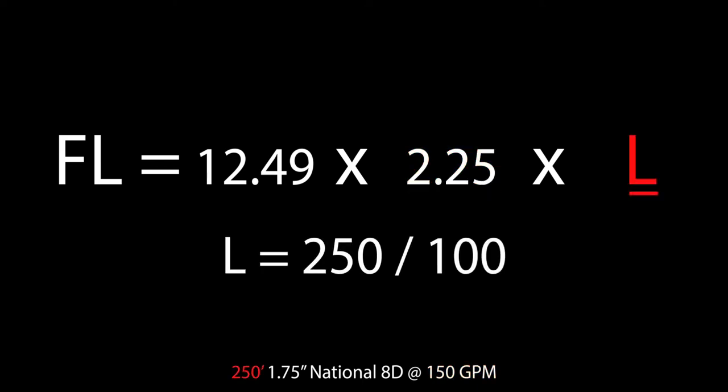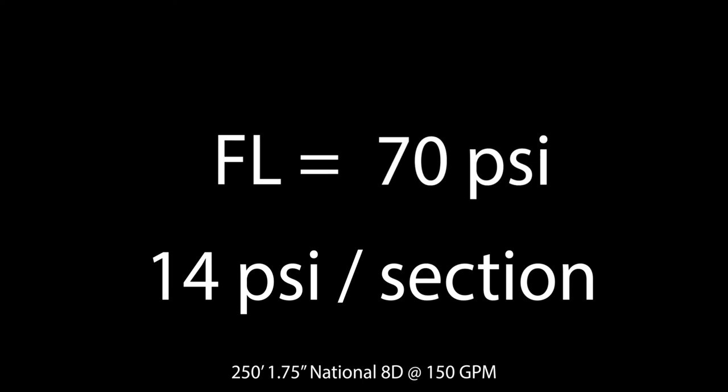Finally, L is our length, 250 feet divided by 100, which equals 2.5. After multiplying these numbers, we obtain a friction loss of 70 PSI, or 14 PSI per section of hose.